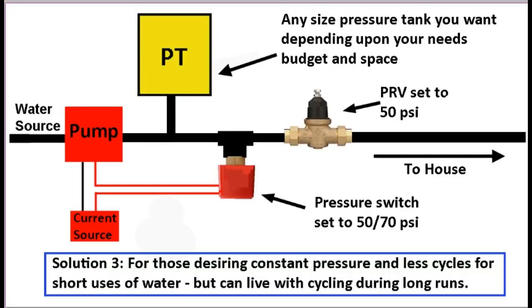So solution 3 is for those that desire constant pressure being the most important thing. And they also want to avoid the pump going on every time they wash their hands or flush the toilet, but they're willing to live with the pump cycling during long runs. It's kind of the opposite of a cycle stop valve. The cycle stop valve will go on, the pump will go on every time you use the water for short runs like flushing the toilet or washing your hands, but it will avoid cycling during long runs. This is kind of the opposite. It will avoid cycling for short runs like flushing a toilet or washing your hands, but it will still cycle during long runs. So let's look at the way this works.